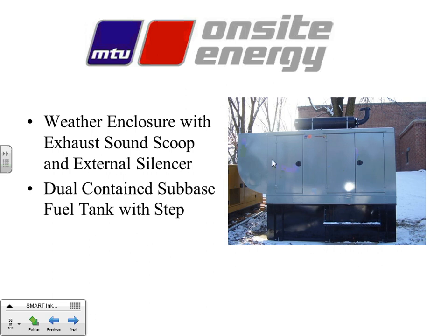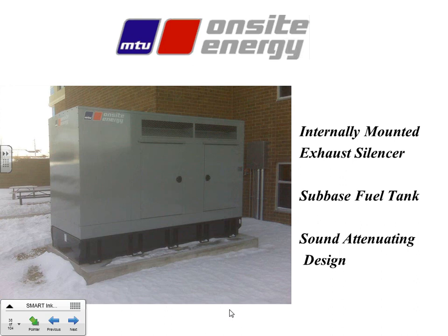Again, this is for some level of sound attenuation. We've got inlet air coming across the unit this way. A radiator sits about here with a pusher fan that's pushing it out and up. Again, we're turning the air up as another means to reduce the sound. Big deal these days in cities and so on. They want them to run quiet. There's a little step. Some of the tanks, because it's a tank within a tank, get a little taller if we want to keep the footprint the same. Again, here's the other one we looked at before with inlet louvers on the top. The air comes in and goes up and around and over and through and then out this way.